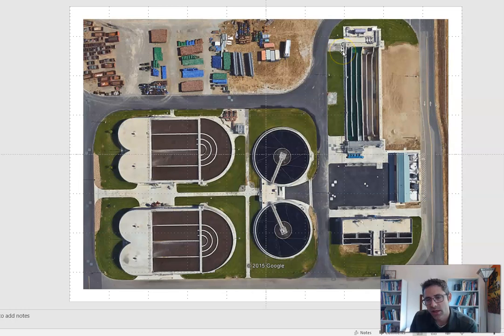So this is a common orientation that uses complete plug flow in a small area and makes the wastewater snake around. It gives the chlorine a long time to do its thing, and also achieves plug flow, which we said before is good for reducing the size of the reactor needed to achieve the removals required.